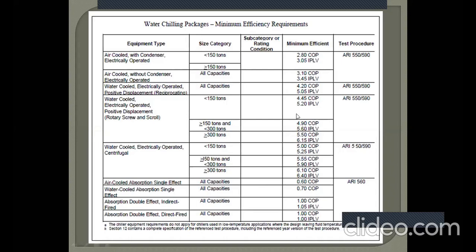But as far as our topic is concerned, you can observe that with centrifugal chillers you get higher COP, but the limitation is that these compressors or chillers are very application specific. So for small capacity you have to go for a screw or reciprocating compressor. Clear?